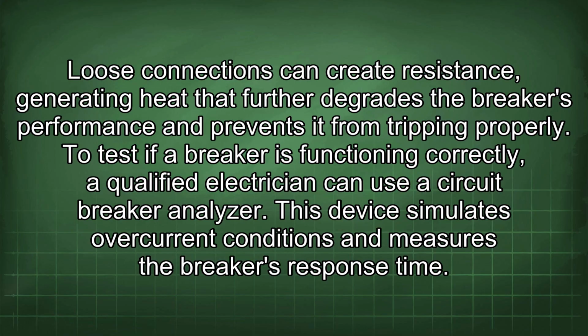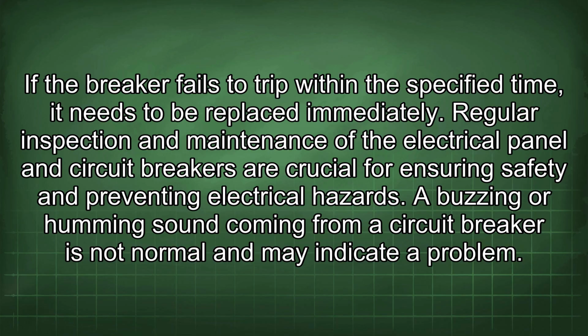To test if a breaker is functioning correctly, a qualified electrician can use a circuit breaker analyzer. This device simulates overcurrent conditions and measures the breaker's response time. If the breaker fails to trip within the specified time, it needs to be replaced immediately. Regular inspection and maintenance of the electrical panel and circuit breakers are crucial for ensuring safety and preventing electrical hazards.